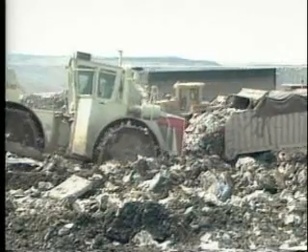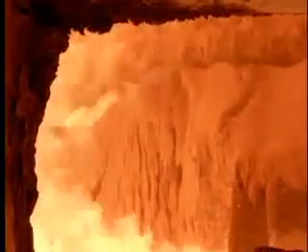The cake sludge kind of looks like soil. It'll either go to incineration, or it'll go to a compost facility, or rarely it goes to a landfill. This is called a multiple hearth furnace. There are 8 different hearths. That rabble arm will rake the sludge around to a drop hole, and it'll go to the next one, and it'll rake around and drop. It's all burned up by the 3rd or 4th stage.